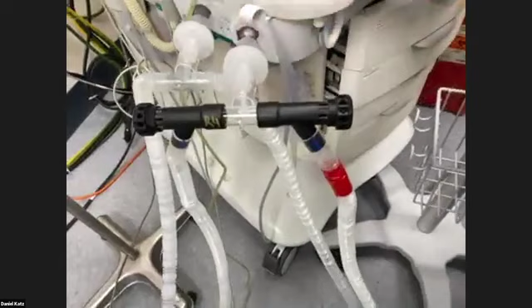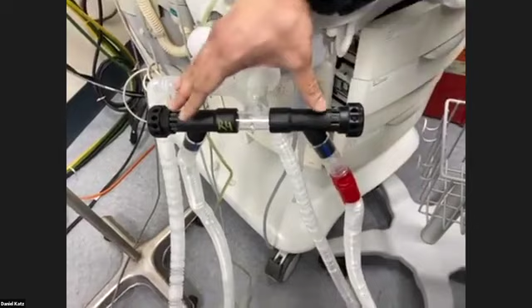Now, if we move on over here, this is the heart of our machine. These are needle valves that are 3D printed, and we can change the amount of flow that's going to one patient versus another patient. This is the inspiratory limb. You have your T piece with your female to female end connector that is connecting between the bacterial viral filter that's back into the inspiratory port of your ventilator. And over here, you also have your one-way valves on your inspiratory limbs as well that help allow the flow of direction in one way as well. Now, we have tested this also on ICU ventilators as well, in addition to this anesthesiology machine.